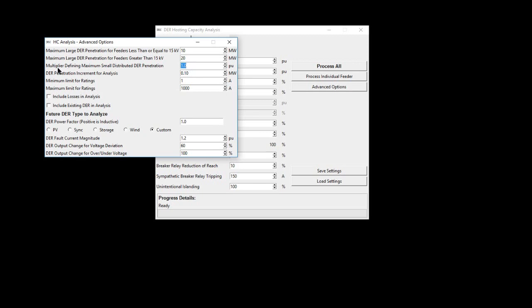The multiplier for determining the maximum small distributed DER penetration is required in the analysis of distributed customer-based DER such as rooftop solar. A multiplier of one defines that the maximum penetration analyzed is equal to the amount of load on the feeder.